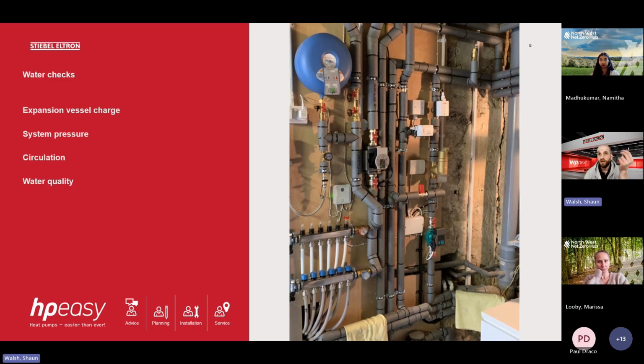If we have blocked filters, blocked strainers, or a diverter valve, for example, that should move in different positions, they can get blocked. And poor water quality can cause all these issues. Okay. So on a regular service, what you should do is check the water quality to make sure it is within the standard range of the heat pump that you're installing. Generally, most manufacturers will give you guidance on what the specific water quality should be and the conductivity levels of the water. So, what else are we looking for when we're looking at water quality?